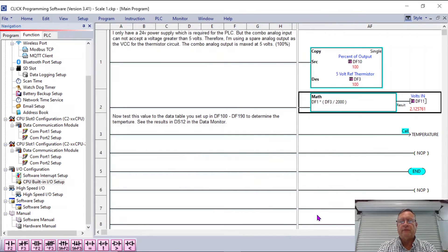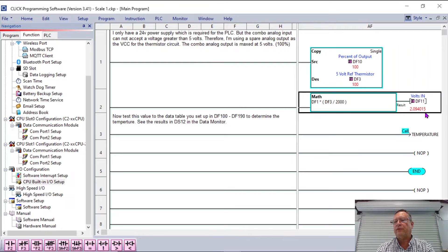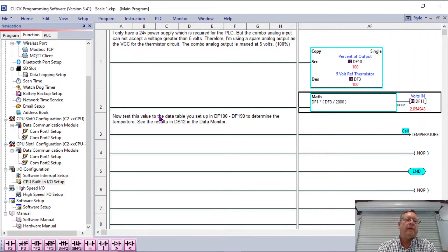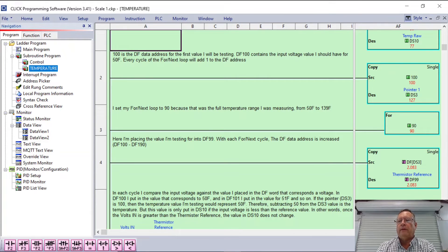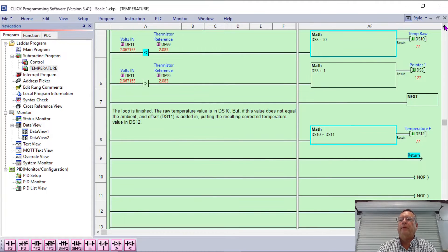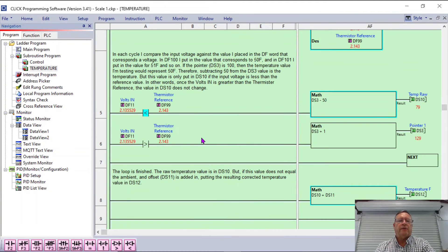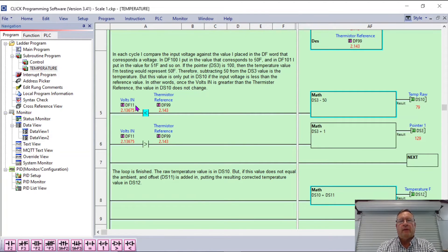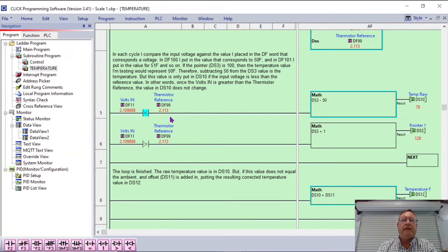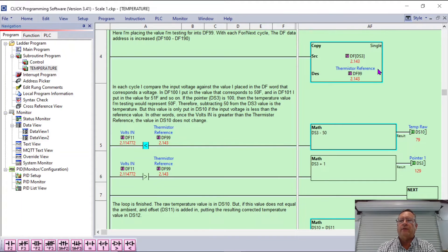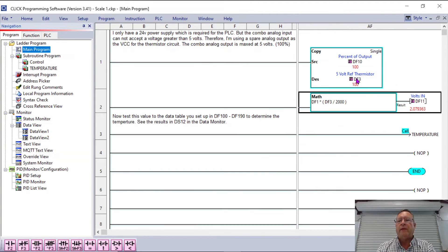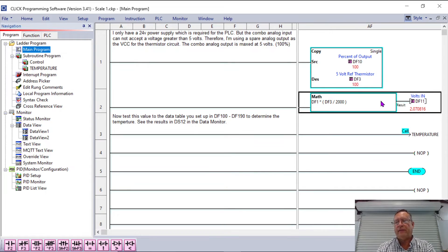Let me cancel from all this. We'll go back to rung number two, you see where I did the little math conversion there. I put that into DF11. Well, if we go back to our program, and we go to the temperature, down here in the NEXT loop, we'll go up a little bit. But here you can see I'm comparing, doing my compare for determining what the temperature is, using DF11 as derived from the analog input. And I'm comparing that to whatever value I put in DF99, which was right here, this rung above. Rather than going through and making changes inside the rest of the program, wouldn't it be easier for me to just not have this at all? Let me take this rung out. I'm going to delete this row.